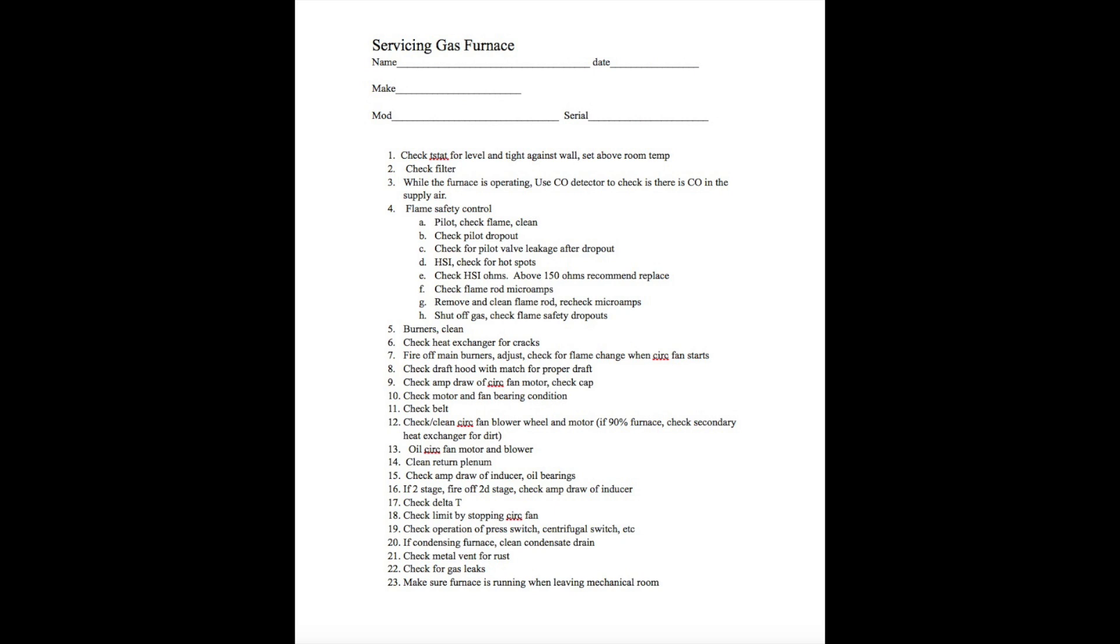On number eight, older furnaces, they have a draft hood. Put a match up to the draft hood. While it's running, the match should be pulled into the draft hood. Now we're going to start checking amp draw.